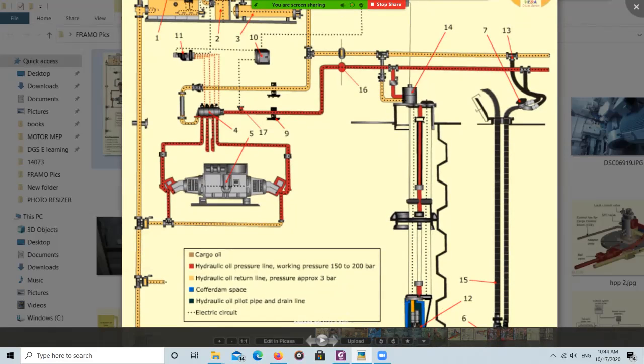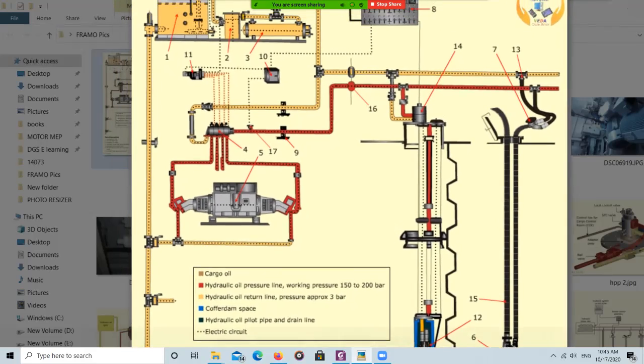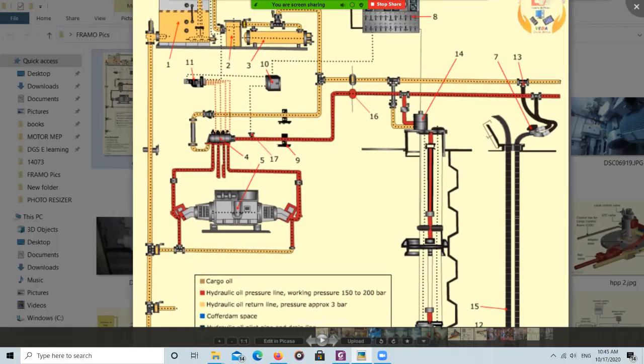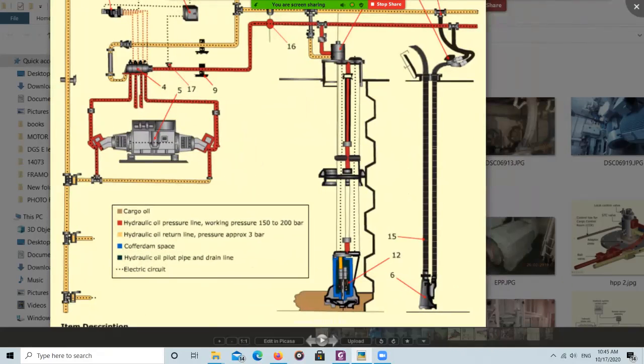From the cooler, the hydraulic oil goes to the variable displacement pump, where the pressure of the hydraulic oil is increased. This increased hydraulic pressure is used to drive the cargo pumps, ballast pumps, and other operations. The generalized hydraulic pressure line is 150 to 200 bar, and the return line pressure is approximately 3 bar. When one jockey pump is running, the system will be at around 2.5 to 3 bar pressure.